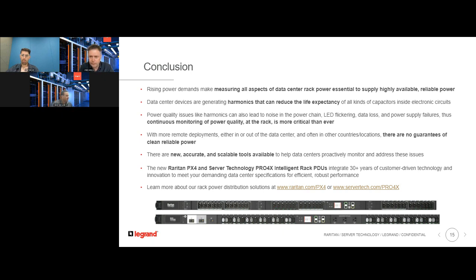And Sven, with that same feature, if there was a network interruption, you don't lose any data either, right? Right, that's correct. And again, that really depends on the real implementation, on the DCIM system you have in place, on the type of protocol you're using. A classical protocol is SNMP version 3, but the more modern DCIM systems also support our REST API so that they can talk with our PDUs in a more sophisticated way and not rely on SNMP. We have also implemented the latest protocol, the Redfish protocol, for rack PDUs. This also helps to optimize the communication between all the distributed PDUs and the central DCIM software.